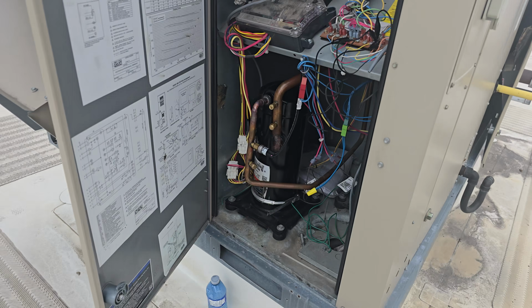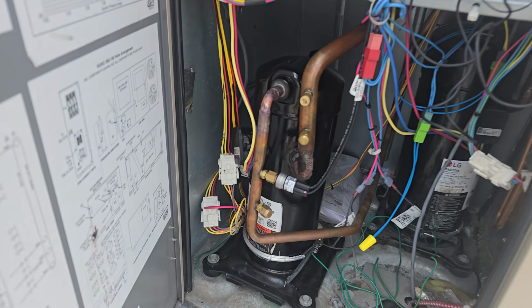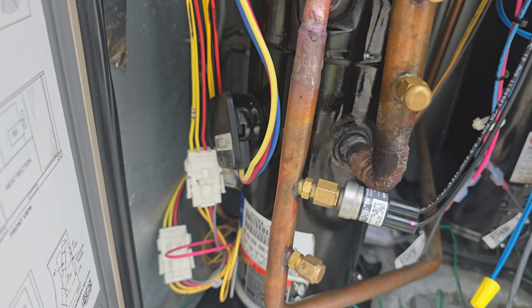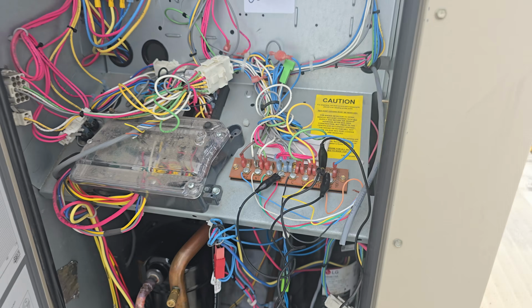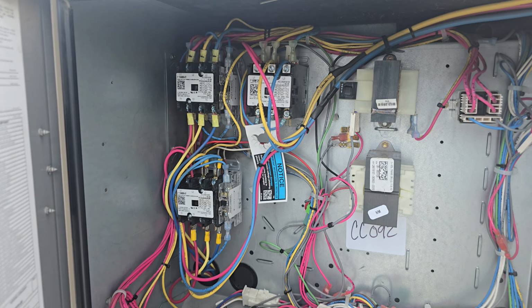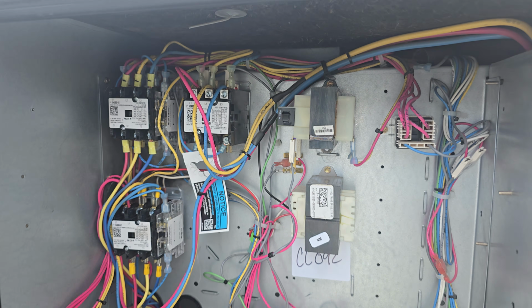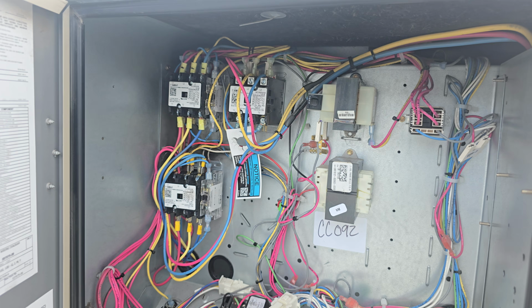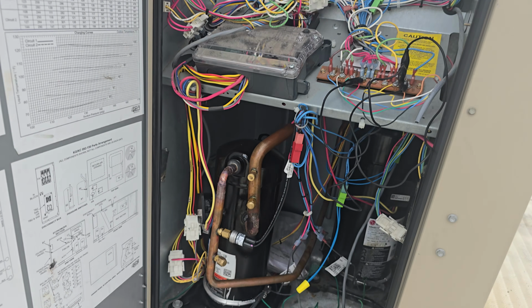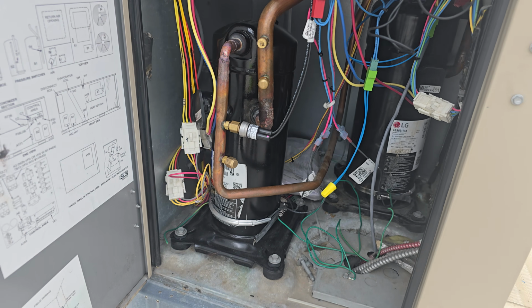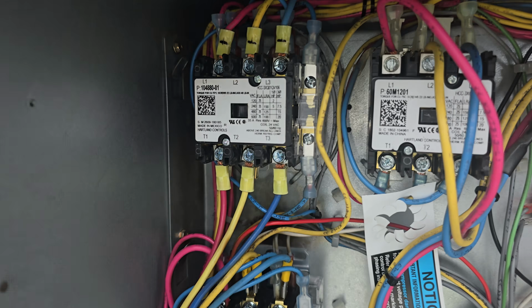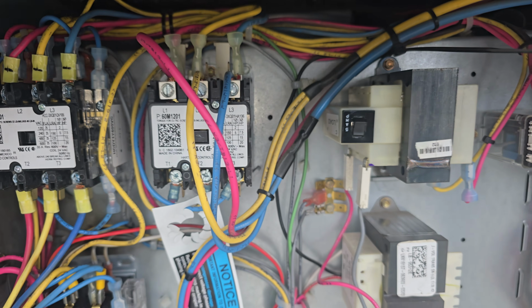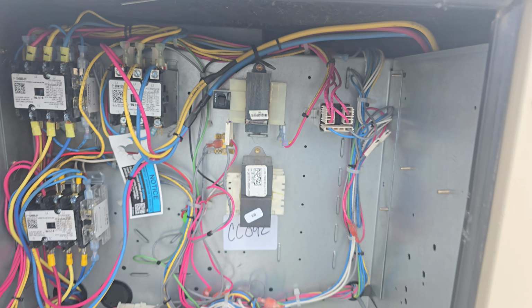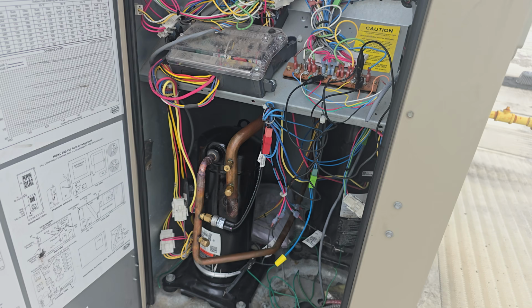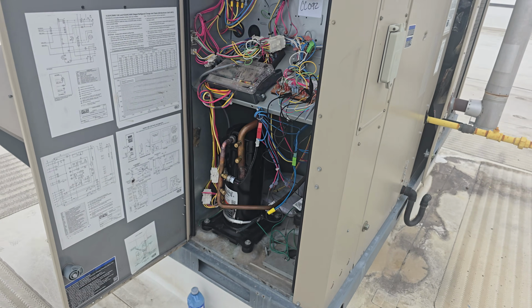Okay, so I hooked up my compressor wiring, and then also my low voltage wiring, and you can see everything seems to be running fine. So I'm just going to take an amps reading and compare it with the nameplate to make sure everything works. So my two compressors have kicked in, and including the blower motor, that has also kicked in. So everything is looking good. So it means this job is completed.